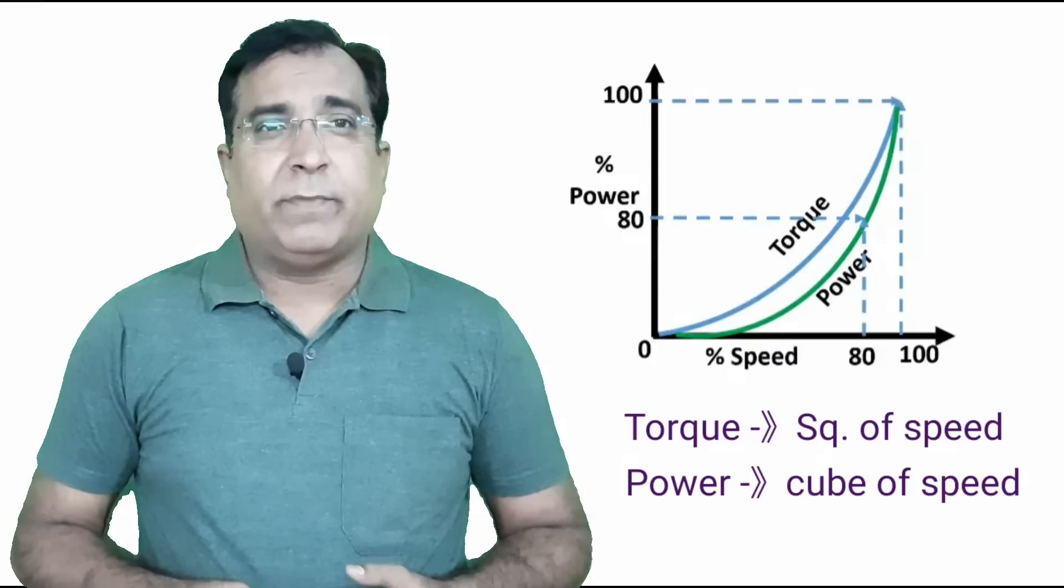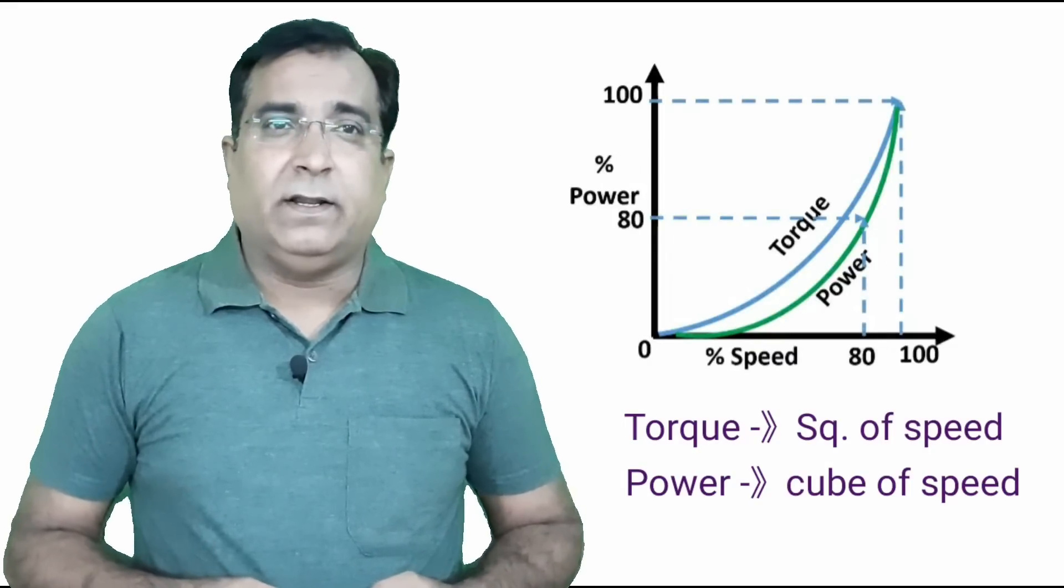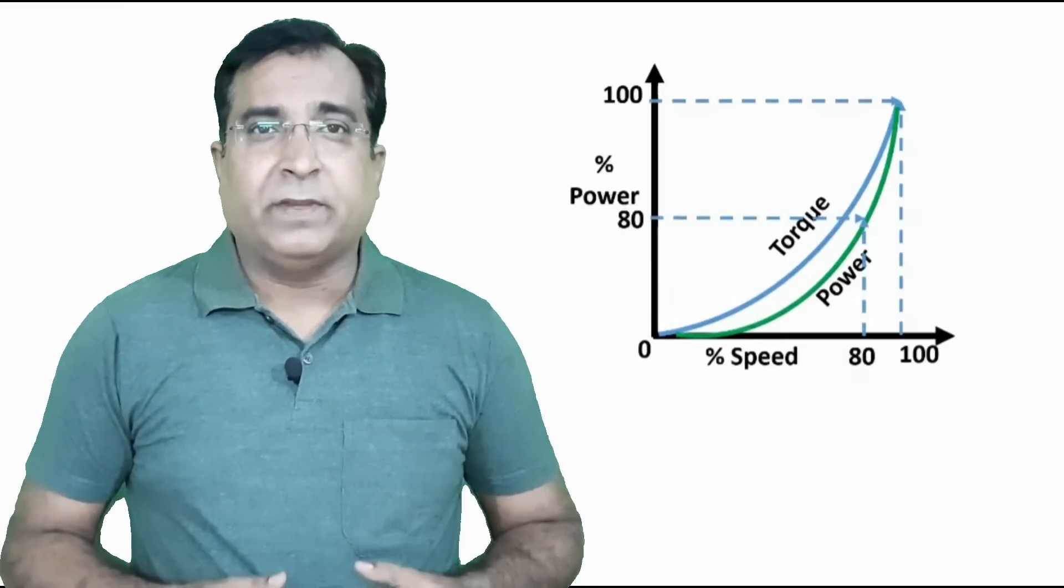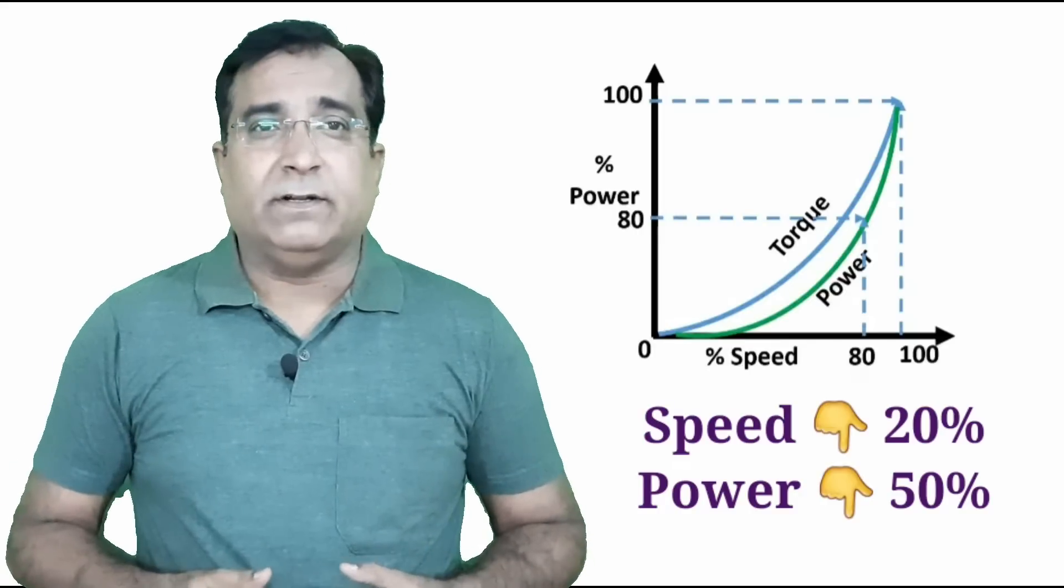As speed is reduced in this equipment, the torque demand also decreases according to the square of speed and power demand also decreases according to the cube of speed. For example, if speed is reduced by 20%, then power comes down to the 50% level.